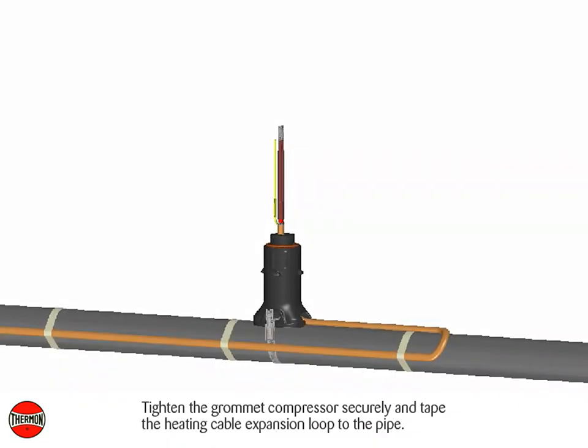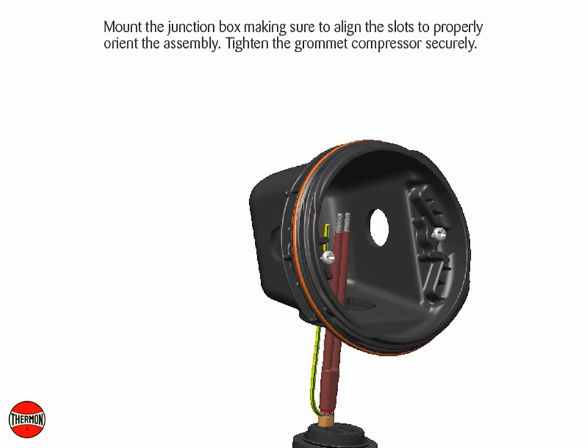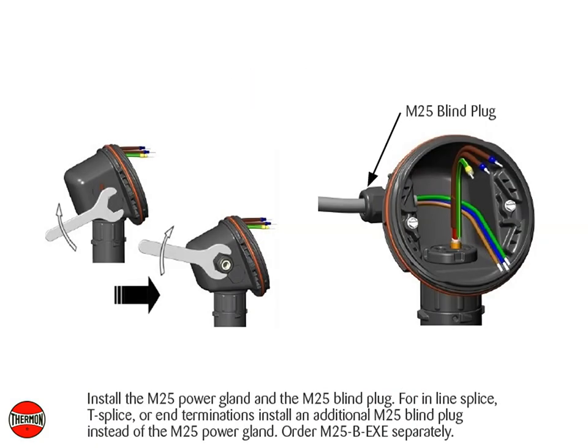Tighten the grommet compressor securely and tape the heating cable expansion loop to the pipe. Mount the junction box making sure to align the slots to properly orient the assembly. Tighten the grommet compressor securely. Install the M25 power gland and the M25 blind plug. For inline splice, T-splice, or end terminations, install an additional M25 blind plug instead of the M25 power gland.